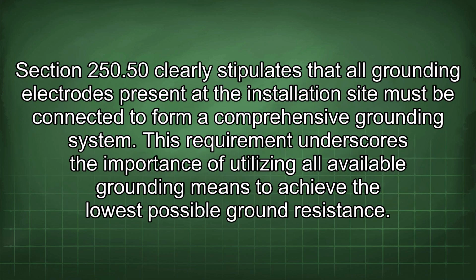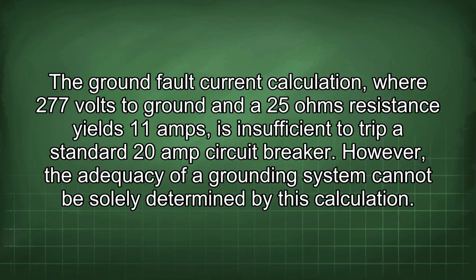Section 250.50 clearly stipulates that all grounding electrodes present at the installation site must be connected to form a comprehensive grounding system. This requirement underscores the importance of utilizing all available grounding means to achieve the lowest possible ground resistance. The ground fault current calculation, where 277 volts to ground and a 25 ohms resistance yields 11 amps, is insufficient to trip a standard 20 amp circuit breaker.